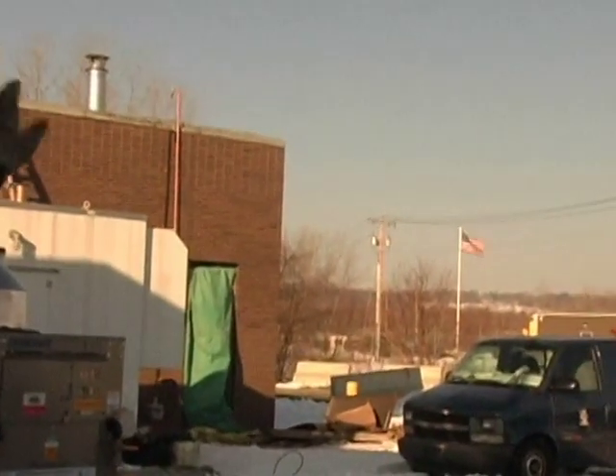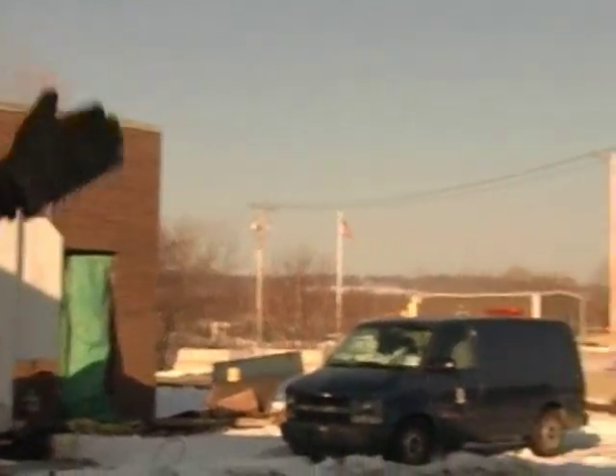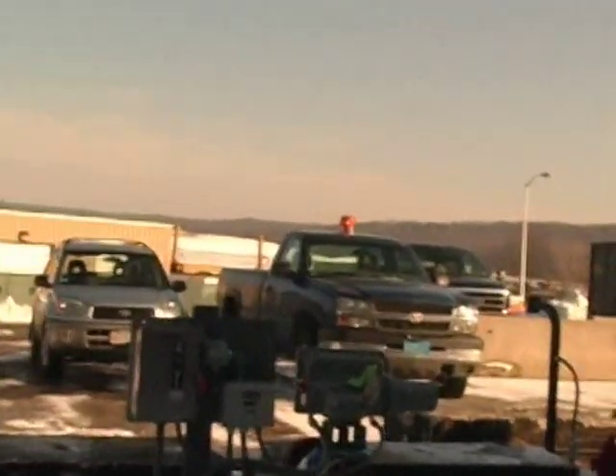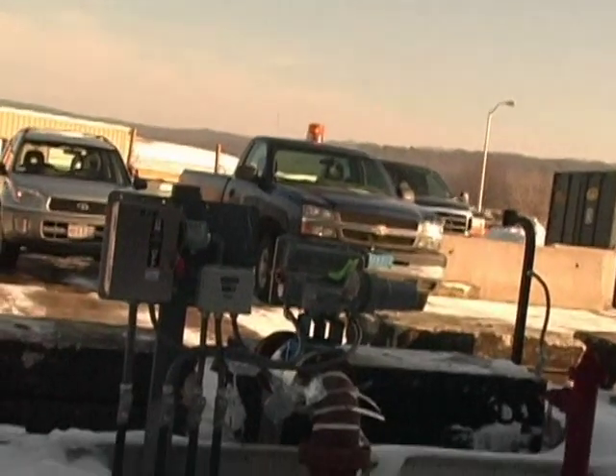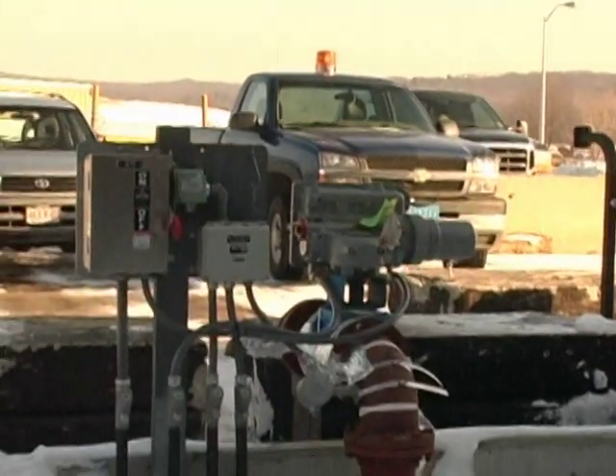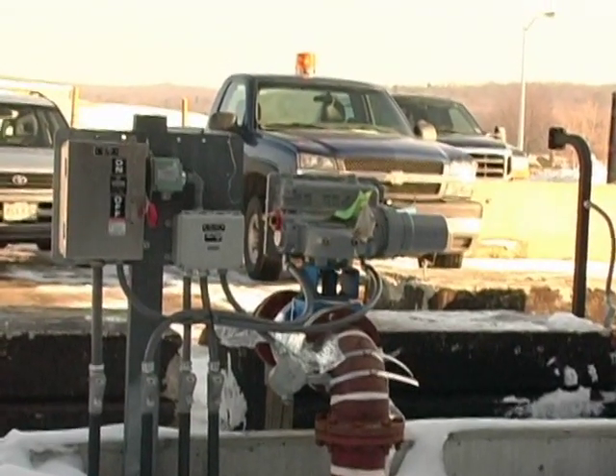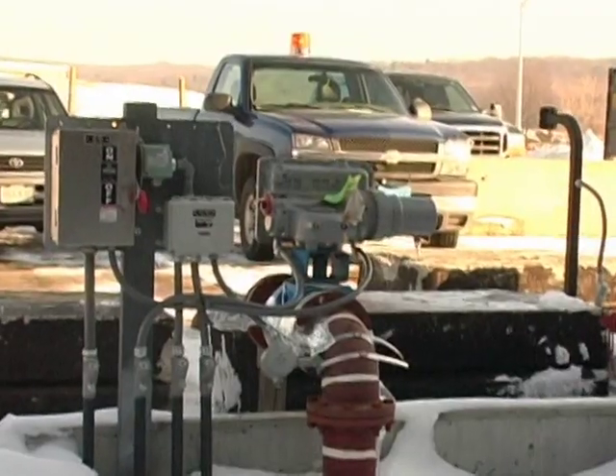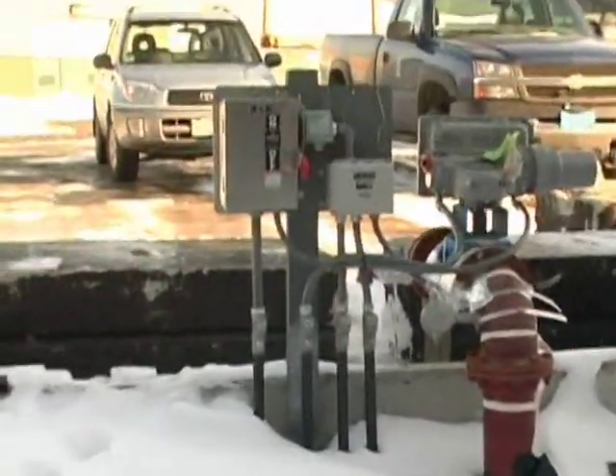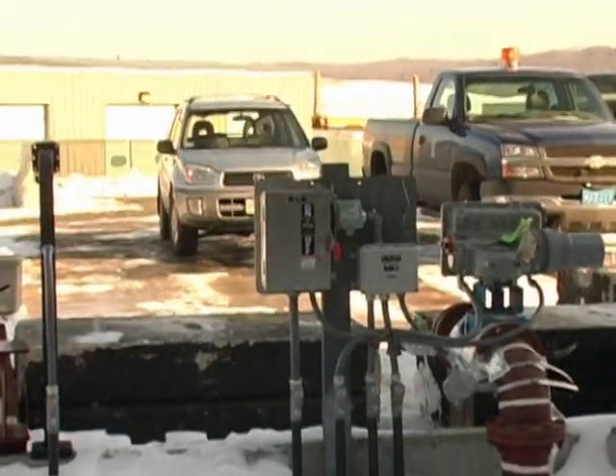So the main flow is coming into the facility at the junction box across the driveway. From there, the 84-inch line feeds under the driveway and enters the facility right here. On the outside of the facility, as we talked about, there are septic receiving stations directly off to my right, behind you. There are card readers associated with that operation, as well as coils within the pavement itself. So once a truck is in the stall and a card has been flashed in front of the card reader and identified as a vendor that you will accept at the facility, then in the automatic mode, the receiving valve will open so that the vendor can then dump the material that he has on the truck.